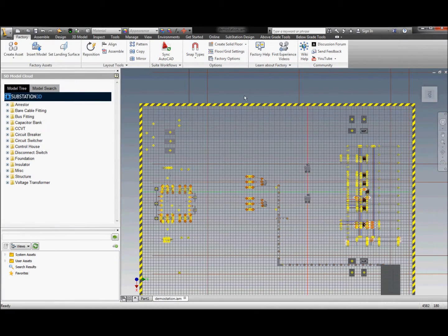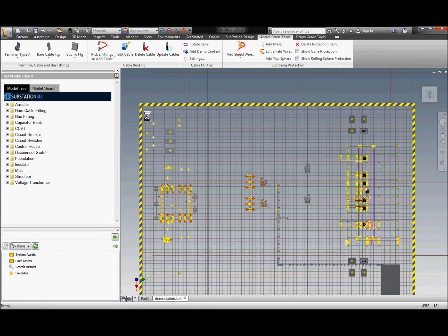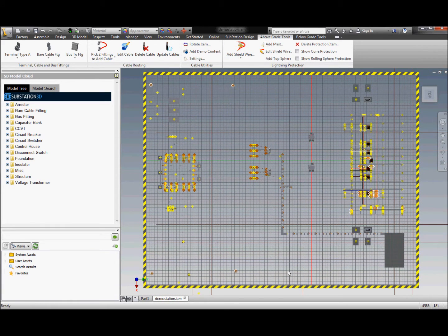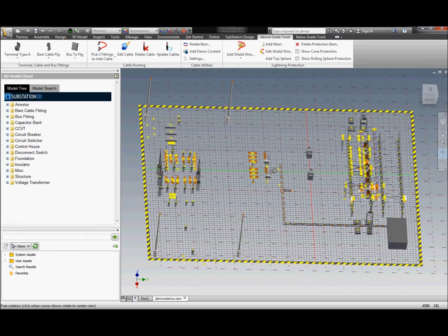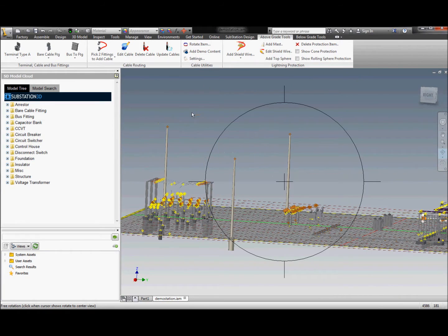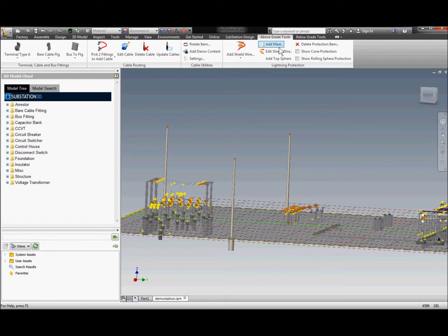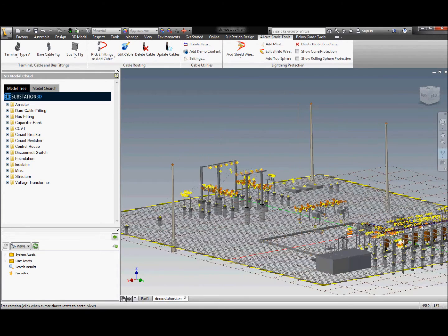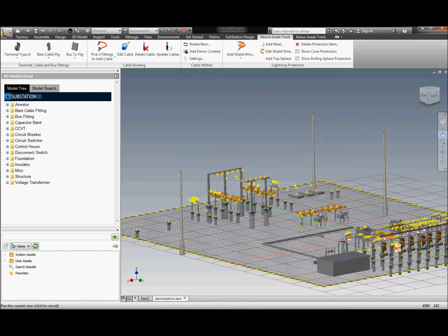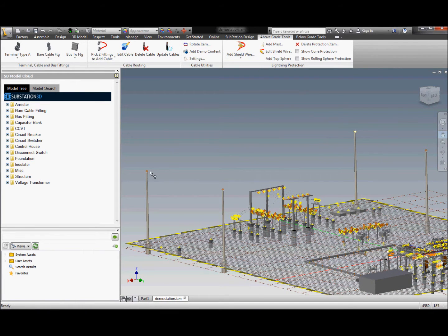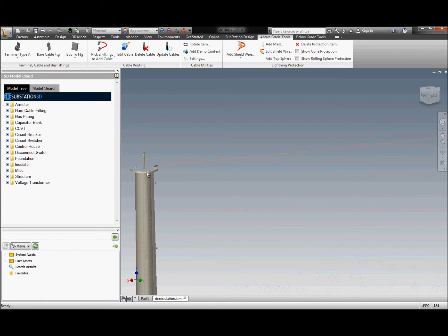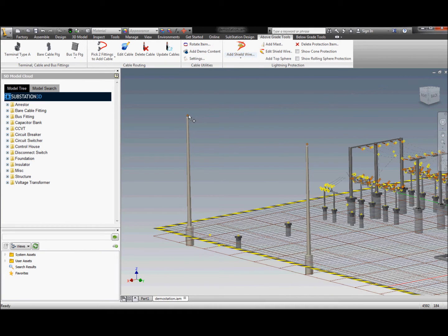The substation design lightning checks give us the ability to lay in some lightning masts at any location we'd like — just picking and placing components within the grid, snapping them to a location or placing them anywhere on that plane. We'll place four around the outside of the station. With a couple of masts in place, we can add some shield wire across the top of the masts — just picking some work points, and the substation tools take care of generating the actual 3D spline that represents the cable component itself. Adding another shield wire across the two masts in the back — the substation tools calculate the SAG based on the size of the shield wire, and when we run the cones you'll see how the cones react to that SAG.